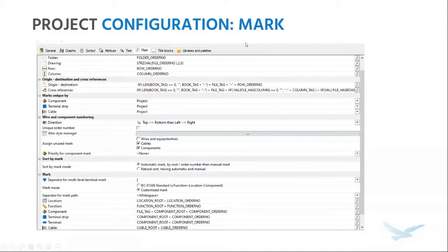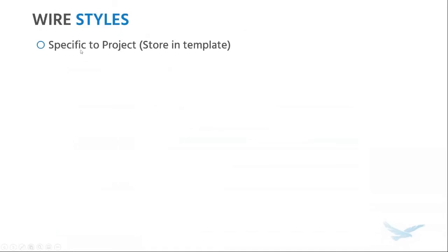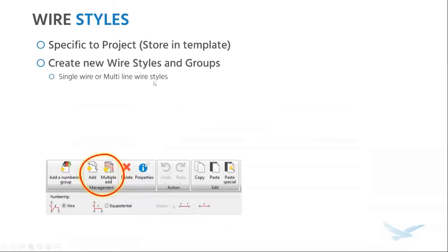Let's move into setting up our wire styles. Keep in mind your wire styles are specific to a project, so ideally store them in a template — there's no wire style library. Create them in your project and store them in your template, so when you use this template to create a new project, all the wire styles from the template are also in your new projects. From the wire style manager, you can create groups as well as new wire styles. These new wire styles could be single-line styles or a multi-line wire style — think control wire versus three-phase power.